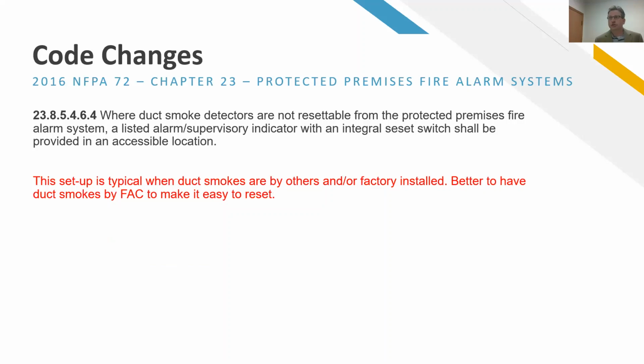So we talked about duct smoke detectors a couple slides ago. And this is in regards to trying to reset those duct smoke detectors, which generally is like a switch. You have to remove power. And this is not my pitch, but it's definitely a good idea to have system duct smoke detectors, because when you hit the reset button on your fire alarm panel, it takes care of all that. If you have factory installed duct smokes, or mechanical puts duct smokes in, and those need to be reset, how do you do that if you don't have a central point where you can actually break power to those detectors? The code is saying you do need to have a reset switch. So that can be a real pain if you have a bunch of factory installed duct detectors. So just something to be aware of there as well.